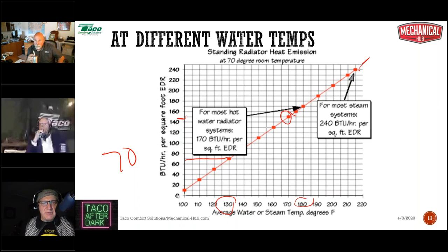What water temperature were we talking about for 170? Well, we answered that. It was at an average of 180 degree average water temperature. And that would only be for a 70 degree Fahrenheit room temperature. Of course, there would be other charts you'd have to look at for different water temperatures, but 70 is about normal. Would you run 180 for cast iron rads then? Well, you could. There's no reason not to.